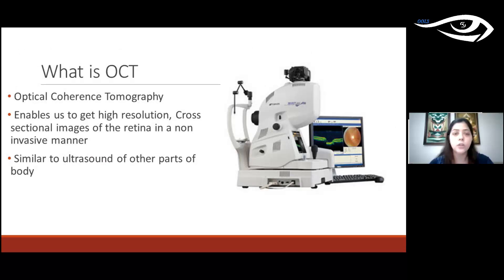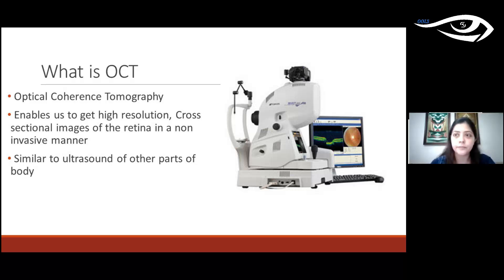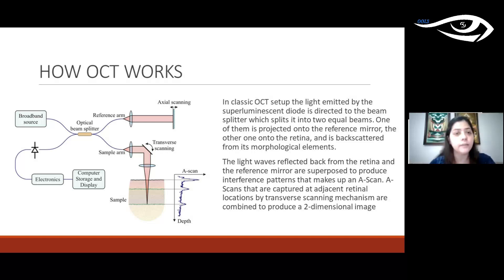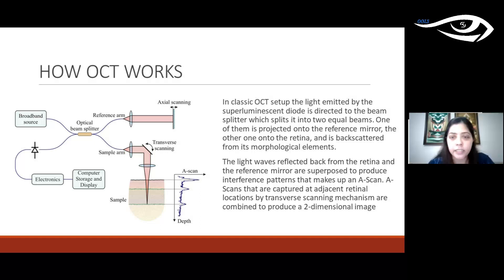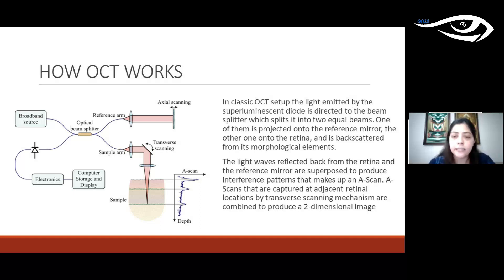OCT stands for optical coherence tomography, which enables us to get high-resolution cross-sectional images of the retina in a non-invasive manner. It is similar to ultrasound, the difference being that ultrasound uses sound waves whereas OCT works using light waves. The OCT has a source of infrared light split by a beam splitter into two parts: a reference arm reflected by a mirror, and a sample arm projected onto the retina, where light is scattered back from the different retinal layers.